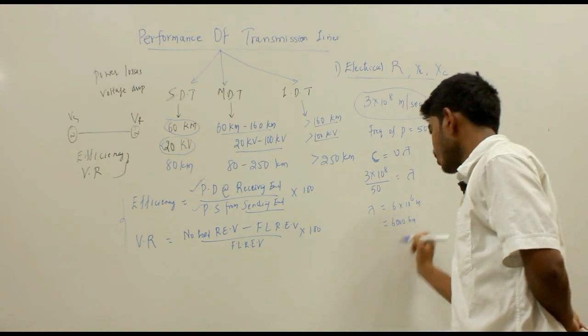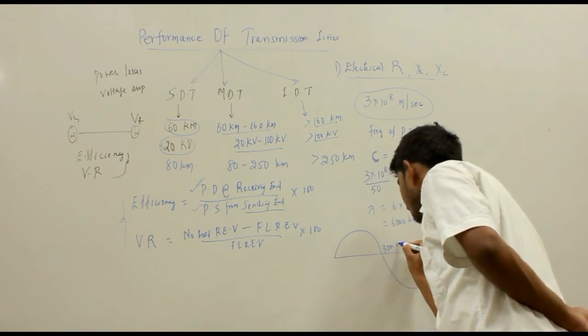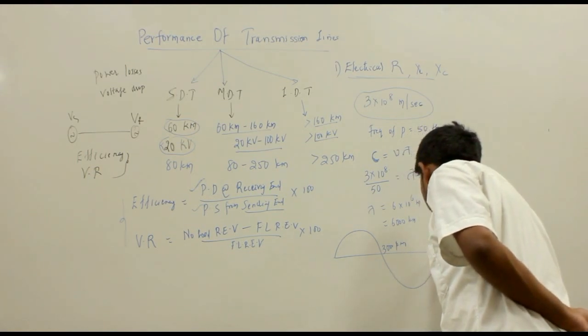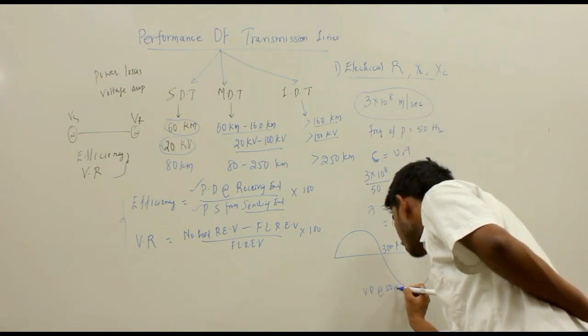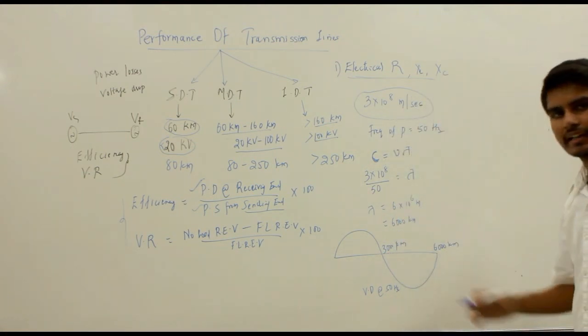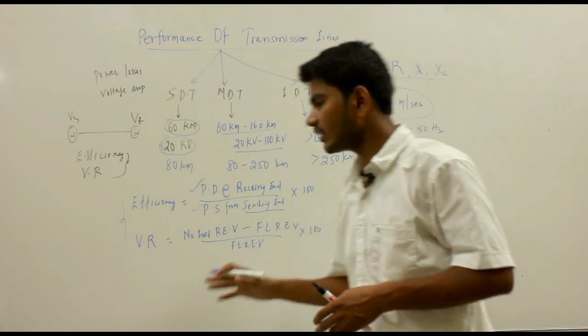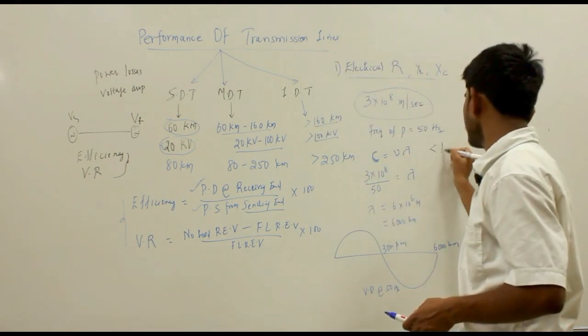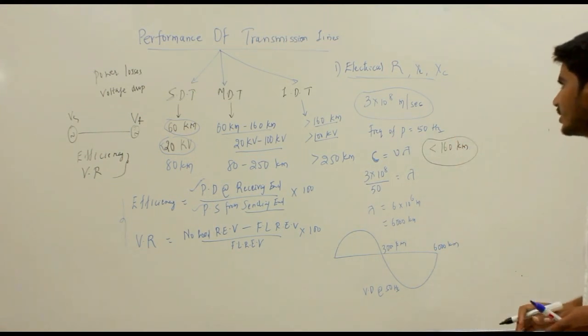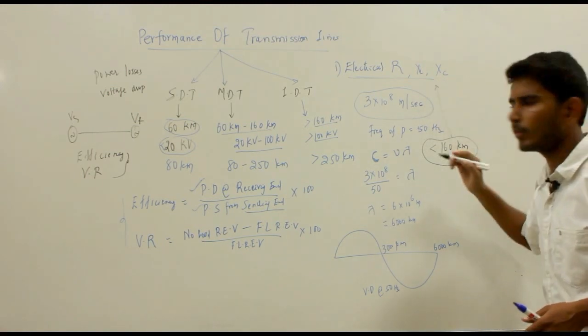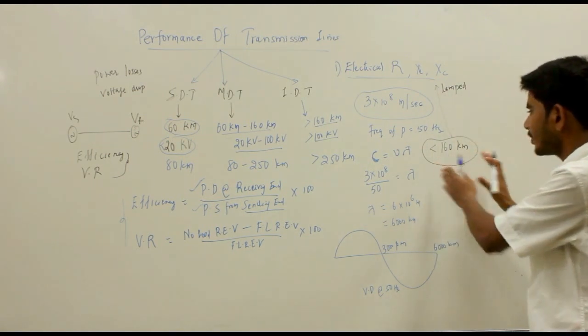Drawing the voltage distribution at 50 Hz, the half-wavelength point is at 3000 km and the full wavelength is at 6000 km. We can see that the wavelength of the power is quite long compared to the normal line lengths we use. For this reason, for transmission line lengths below 160 km, these parameters are assumed to be lumped together rather than distributed.